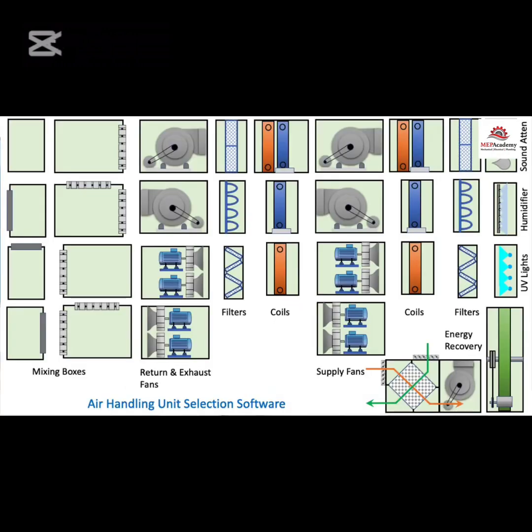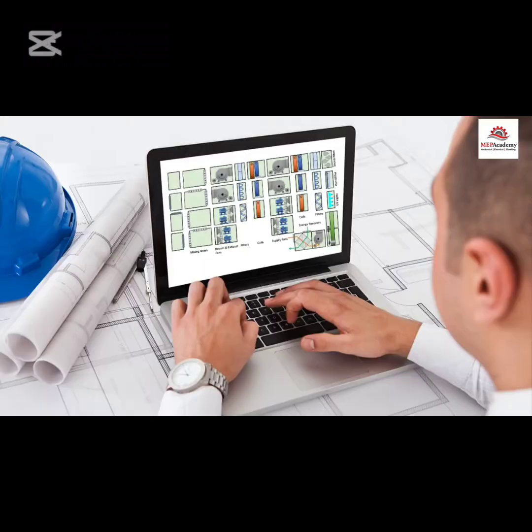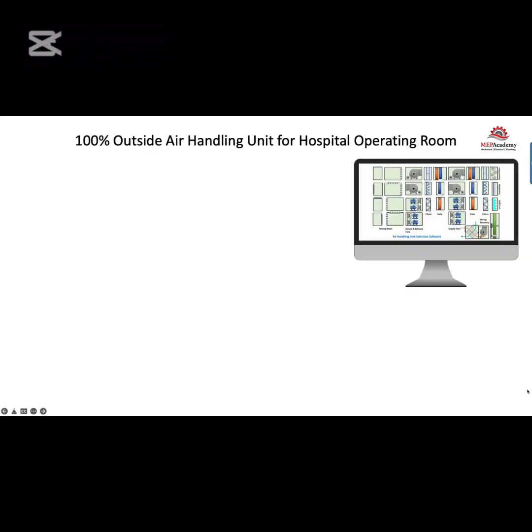Let's build a custom air handler like the manufacturer would using the engineer's project requirements and the available air handler sections. The air handling unit manufacturer will use their software program to assemble a unit based on the project specifics. Looking at a screen of options, the air handler's engineering team will start building the air handler, maybe starting with the inlet options. Okay, now using the manufacturer's software, we can build an air handler for an operating room.